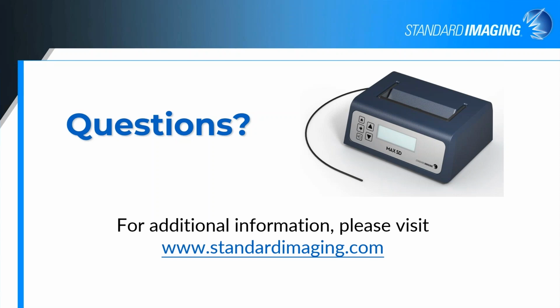Does the smaller size cause positional uncertainties? It can if you're not setting it up very well. Depending on your system, right? What I generally tell people to do with our water tank when they're aligning the device in the water is to align really to the tip of the fiber, because that's way easier to see than any other marker that we could put on the detector, and then step it forward in your water tank 1.3 or 2.3 millimeters in order to get past the light tight cap and to the middle of the active portion of the scintillator.